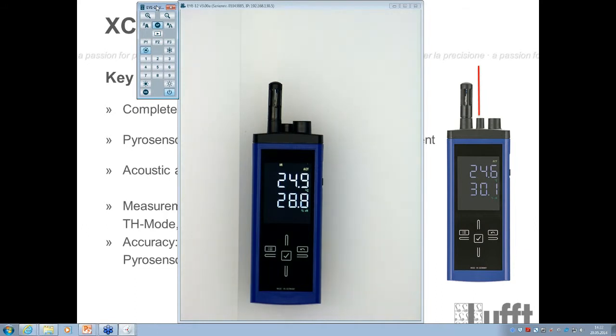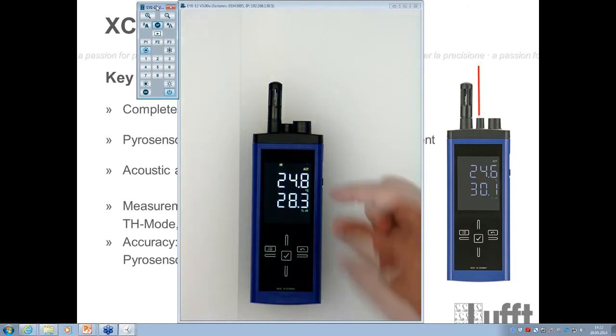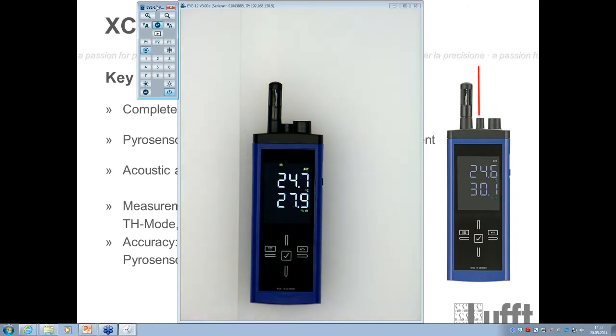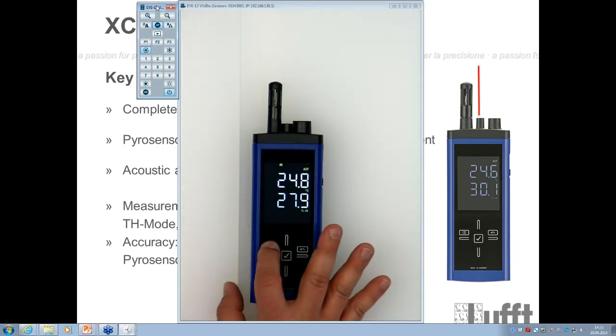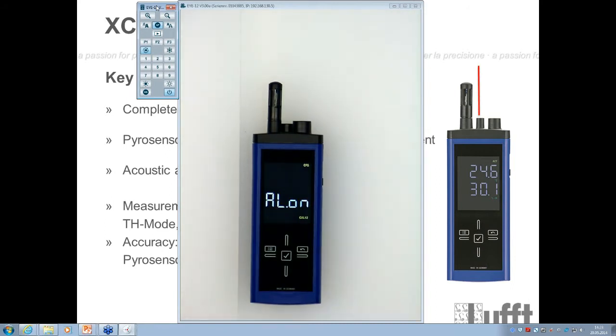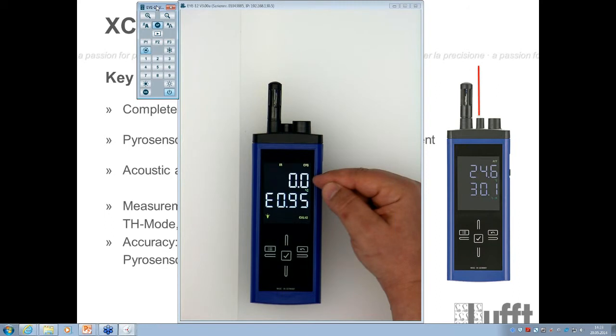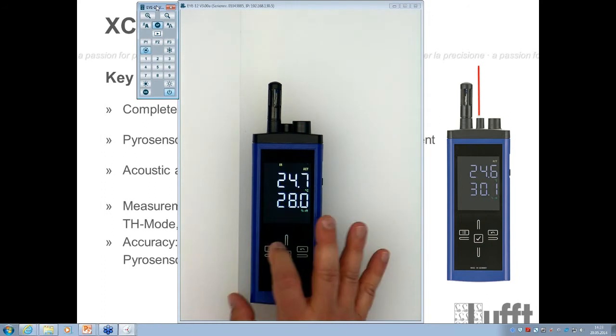So now if you want to change something in the configuration in the IR mode, you can also use the configuration button here. Again, it's the same principle. You have to choose the right combination which you want to use, and if you see that on the screen, you will be able to change the configuration with this button. So now we go enter here, and again you have, of course, always on here. And if you go to Cal 1, which is for the temperature offset, which is this, you will also see E0.95, which is the emissivity value which you can enter.